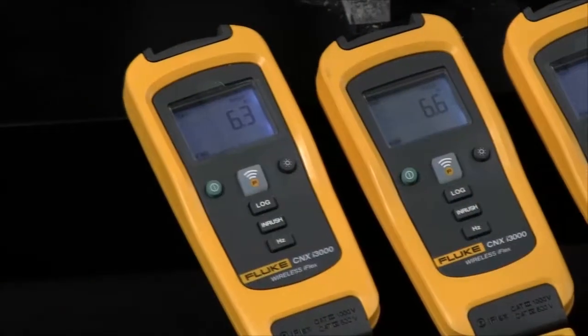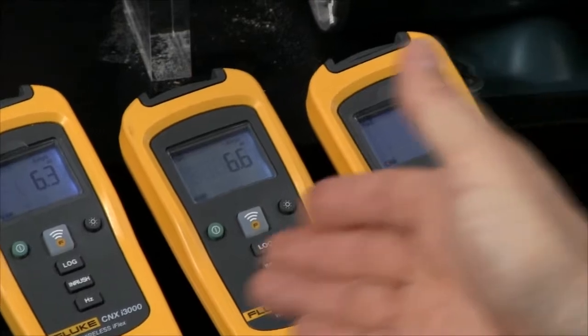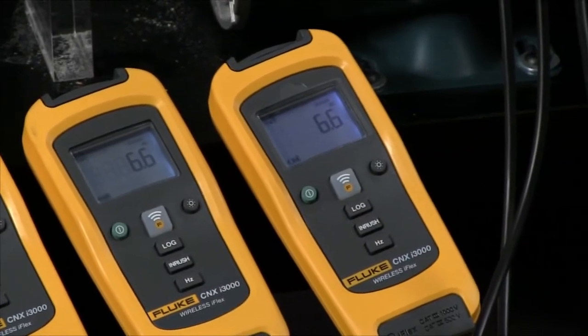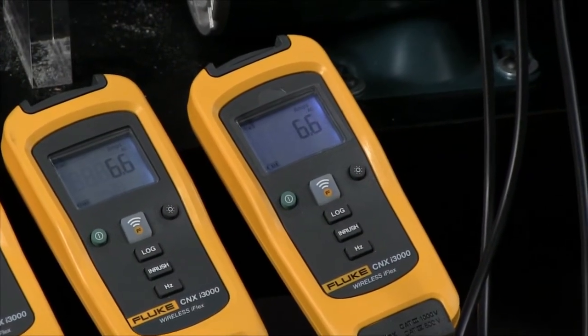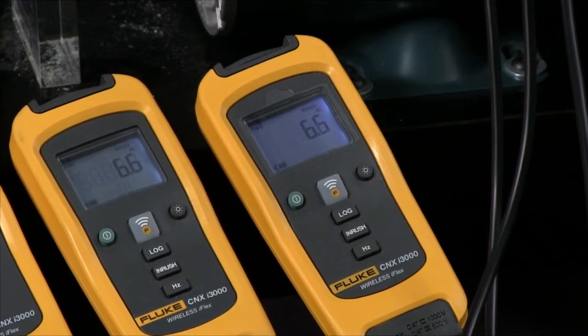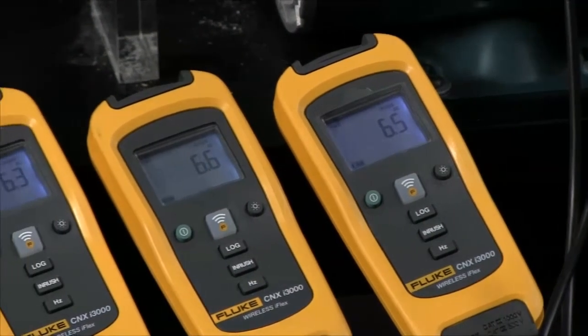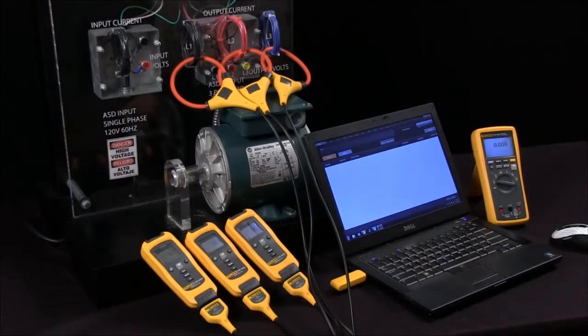One would be to read directly off the screens. You see on each of the i3000 iFlex modules, we were reading the current reading on there: 6.3 amps, 6.6, and 6.6. These are on the respective phases L1, L2, and L3.